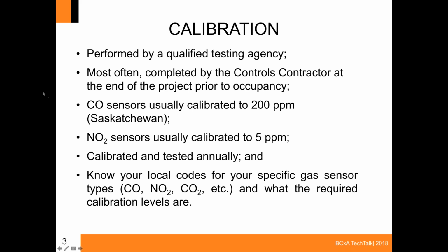If it's just a little parking garage, like in a police station where they're bringing in prisoner transport, those levels are usually a little bit lower on the CO, down to 100 ppm. They need to be calibrated and tested annually by code up here, and it's important to know for your local codes whether you only need to monitor the CO and NO2, or whether you also need to monitor things such as carbon dioxide or others. In Saskatchewan, we don't allow propane-powered vehicles or natural gas vehicles in our parkades, so there may be other gases that you need to monitor for, and you would need to know what the calibration levels are.